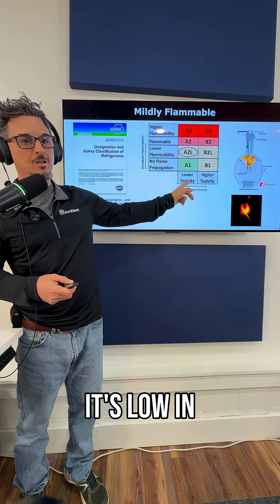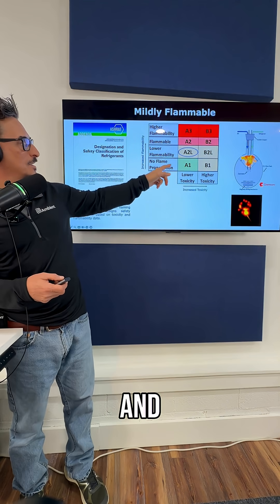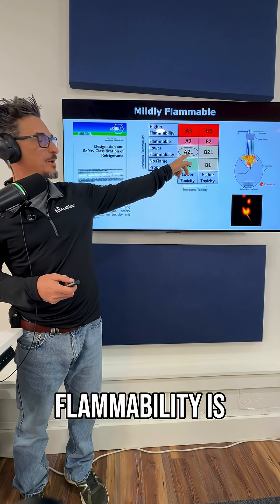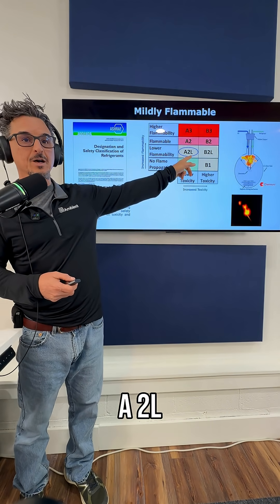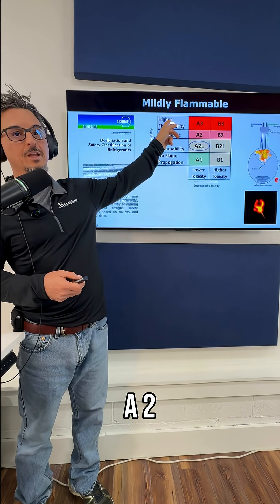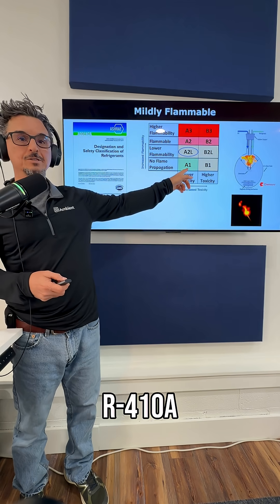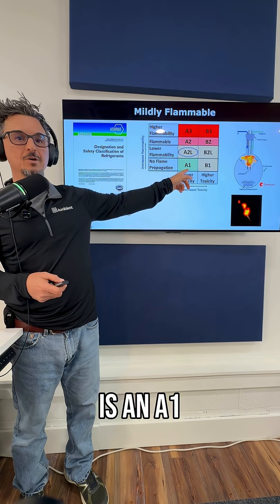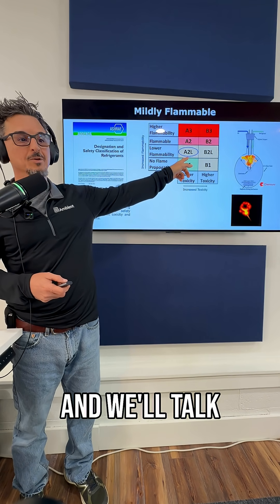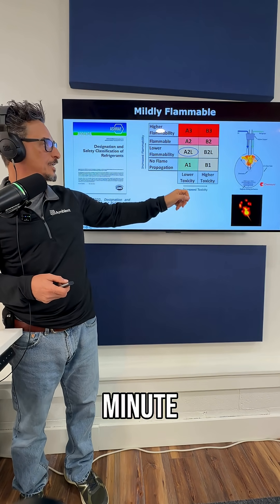When you see A, it's low toxicity; B is high. No flame propagation is a 1, lower flammability is a 2L, flammable is a 2, and high flammability is an A3. R410A is an A1 refrigerant, so now we're moving up to an A2L, and we'll talk about why that's a big deal in a minute.